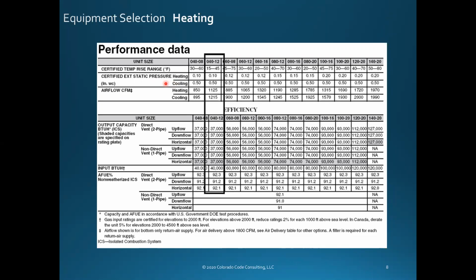What this means is that they don't run the fan at all the different statics, at all the different speeds that the furnace might have. The furnace might have 3 or 4 taps, as they call it: low speed, medium low, medium high, and high. That would be 4 speeds, and they would have CFM at each speed. Well, all they did is run it at a 0.1 external static pressure to get the fan speed for heating. They ran it at a 0.5 to get the cooling speed, okay?